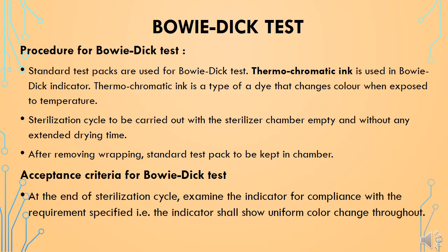For the Bowie-Dick test procedure, standard test packs are used. Thermochromatic ink is used for the Bowie-Dick indicator — this is a type of dye that changes color when exposed to temperature. The sterilization cycle is carried out with an empty chamber and without any extended drying time. After removing the wrapping, the standard test packs are kept in the chamber. The acceptance criteria is that after the end of the sterilization cycle, an even or throughout color change of the indicator should be observed.